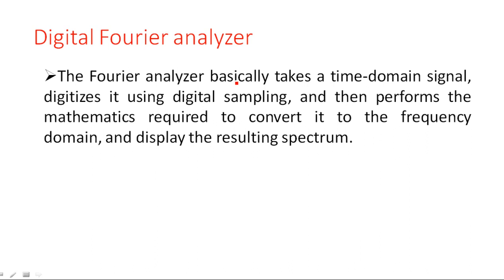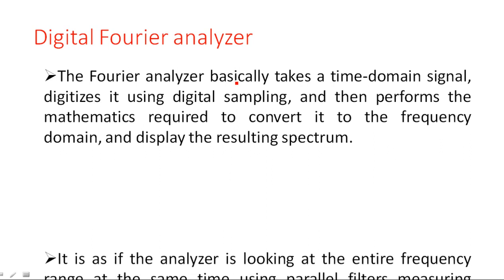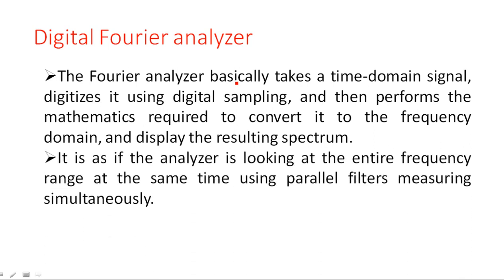The Fourier analyzer basically takes a time domain signal, digitizes it using digital sampling, and then performs the mathematics required to convert it into frequency domain and display the resultant spectrum. It is as if the analyzer is looking at the entire frequency range at the same time using parallel filter banks measuring simultaneously. To get a narrow frequency spectrum, the signal passes through parallel filter banks to measure frequencies simultaneously.